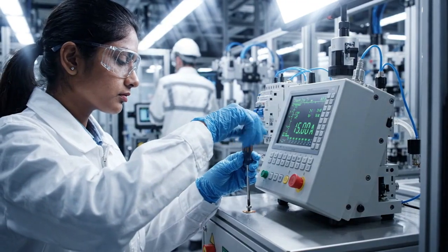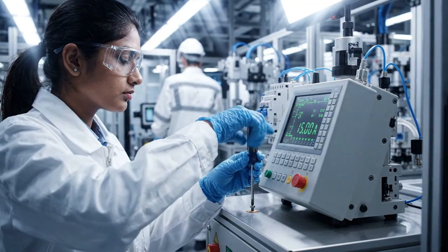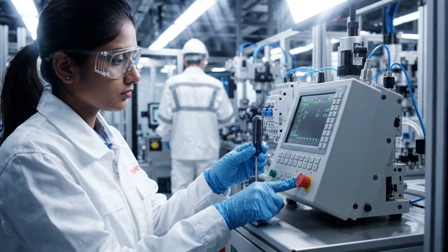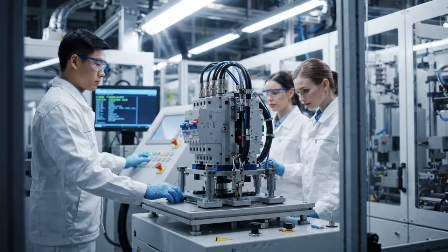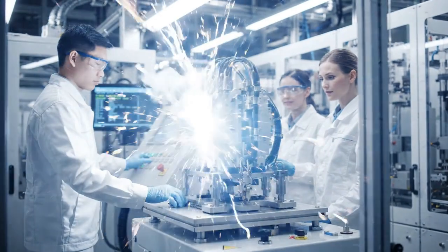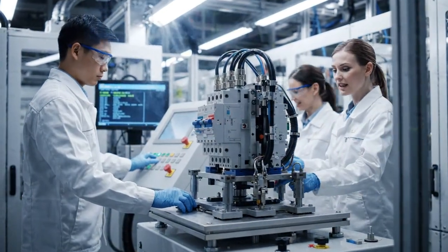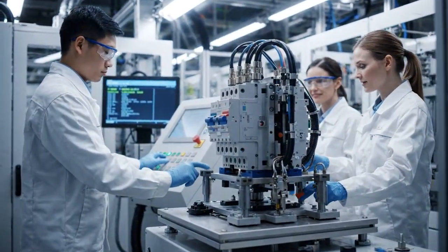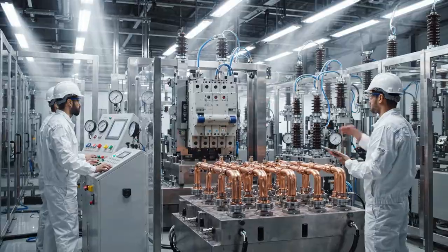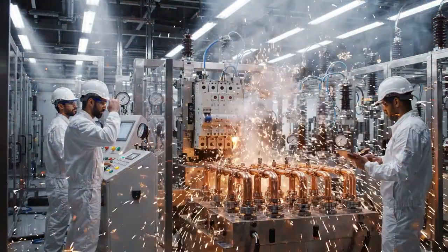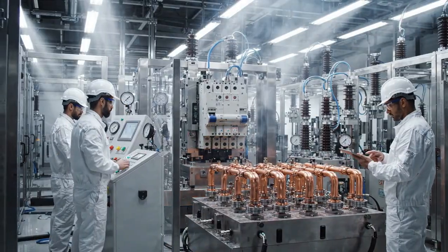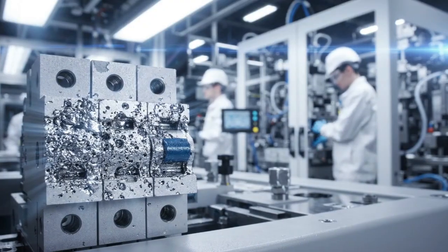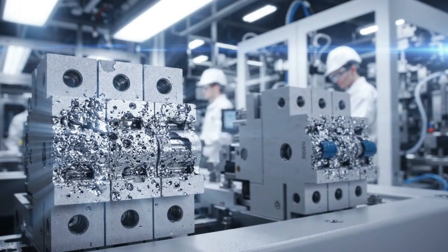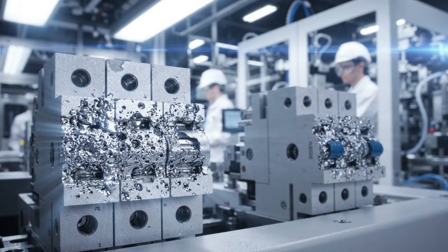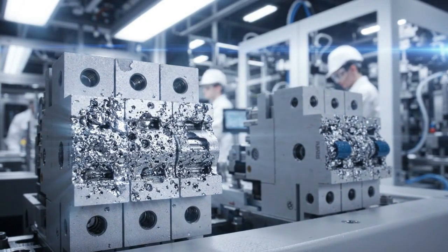Thermal calibration adjusts each breaker to trip at exactly its rated current. A 15-amp breaker must trip within the specified time. Magnetic trip testing verifies the breaker responds to short circuit current within 10 milliseconds. This fast trip prevents the massive fault energy from damaging the protected circuit. After interrupting a full short circuit, the contacts must remain functional. They show arc erosion marks but must not be welded together or mechanically damaged.